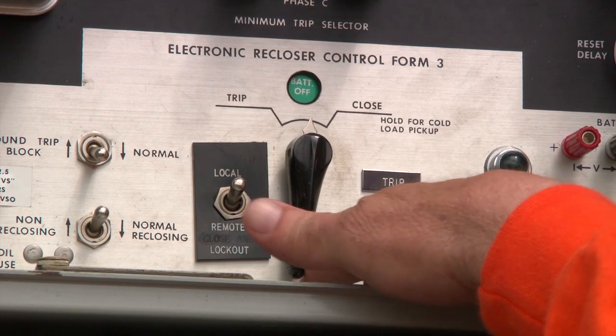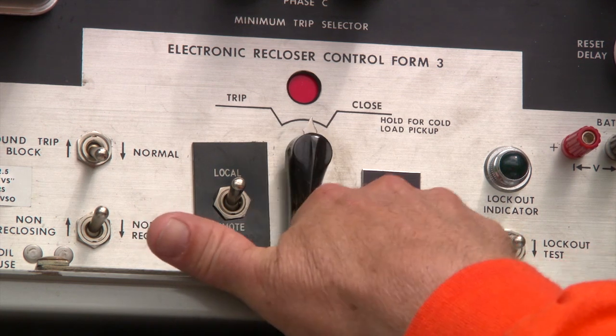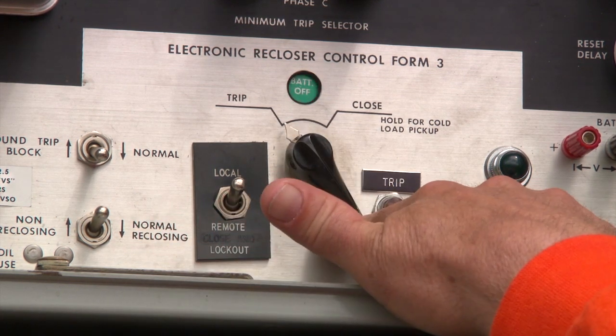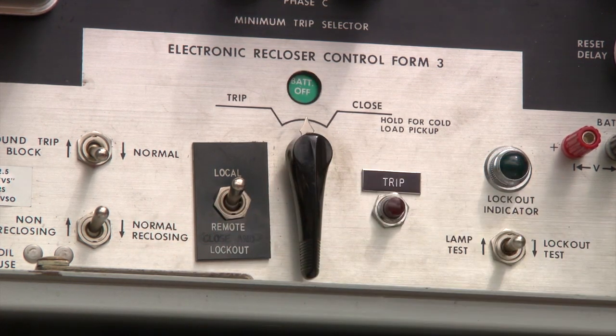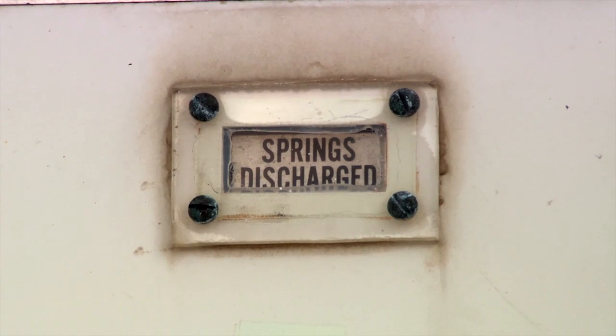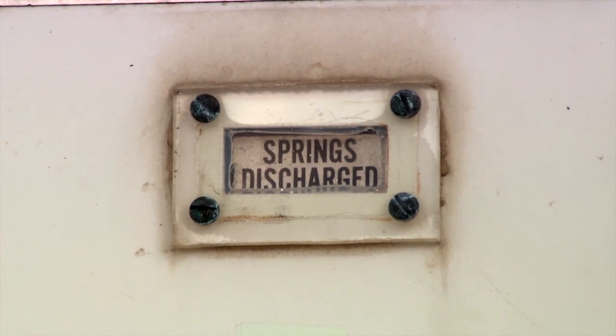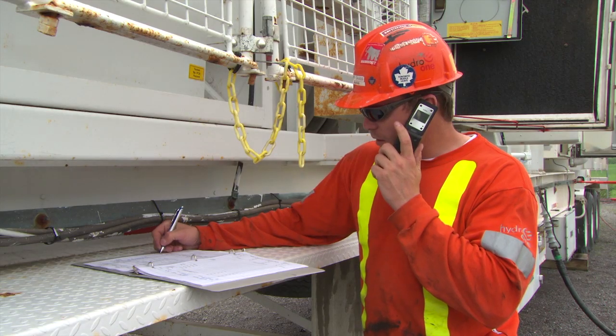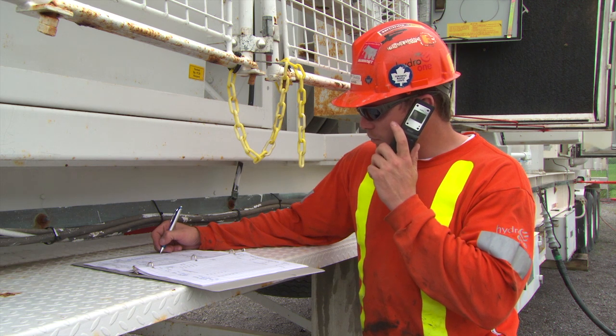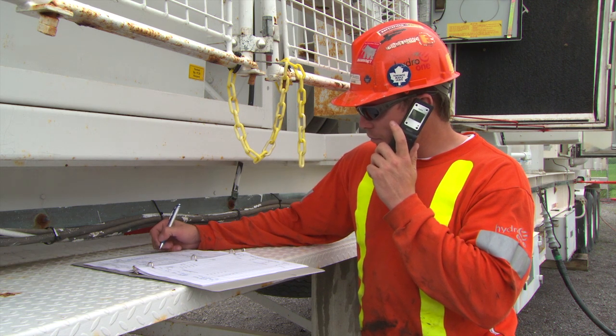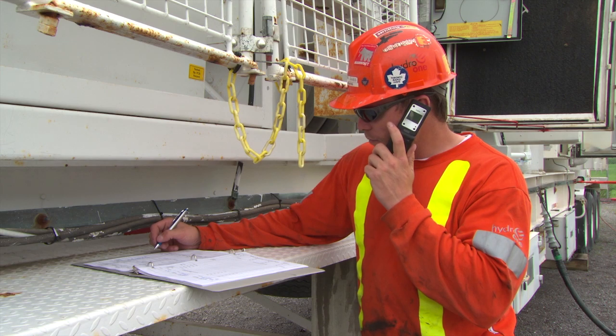Discharge the MUS reclosers by performing the close and trip operation. Verify the F1 and F2 reclosers tripped and closing springs did not recharge. Surrender the work permit. Call the controlling authority to surrender the hold-off and inform them of DS and MUS status.